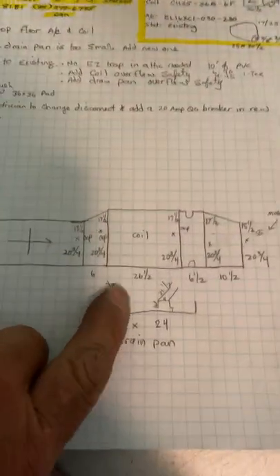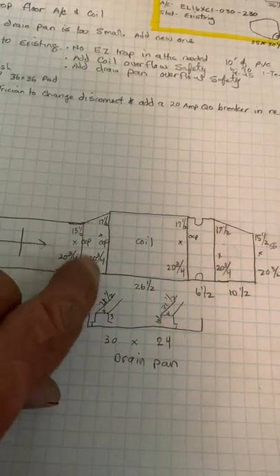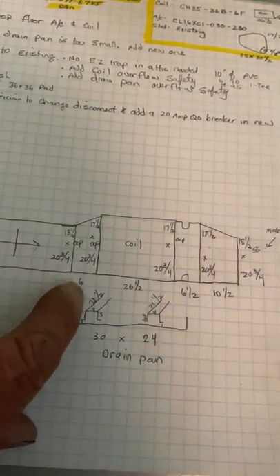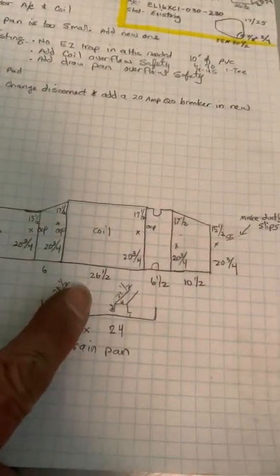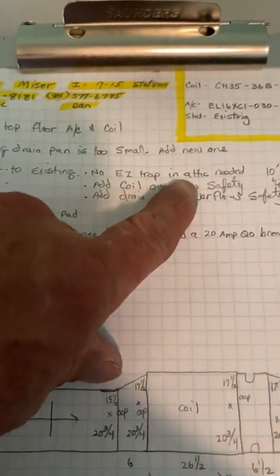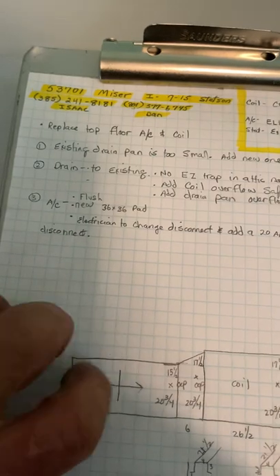So we have the existing furnace. Coming out the right-hand side, you need a minimum of a six-inch piece between the coil and furnace. Then we have the coil, then a canvas, then an adapter, and this is ductboard. The existing drain pan up there is too small — it's only 24 inches — so I made a new drain pan and legs to put under it. Drain to the existing, no EZ trap needed in the attic. Add a coil overflow safety switch and a drain pan overflow safety switch.